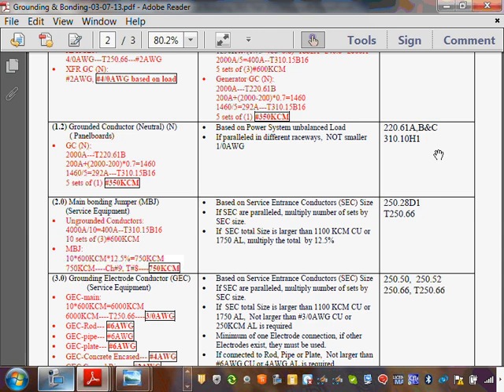That's the worst scenario. The best way to size it is you know the balance, what the 3-phase loads are. All of your 3-phase loads will not contribute to the neutral, throw them out. Then your lighting, 277 in this case, is the only one that's going to contribute to sizing your neutral. But remember, no matter what you do here, when you're paralleling, can you go less than 1/0 anyway when you parallel? So that's how they catch you. If you're paralleling, even if you came up with number 6, a ground conductor, can you do that? You have to go 1/0. Okay, so that's my sizing of the neutral for this system.